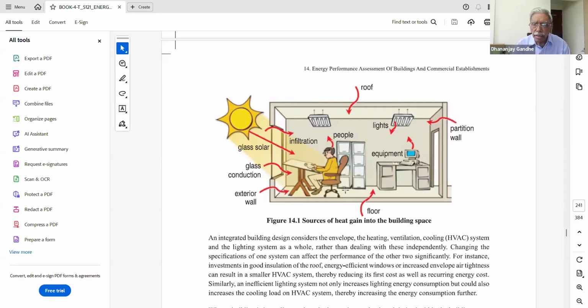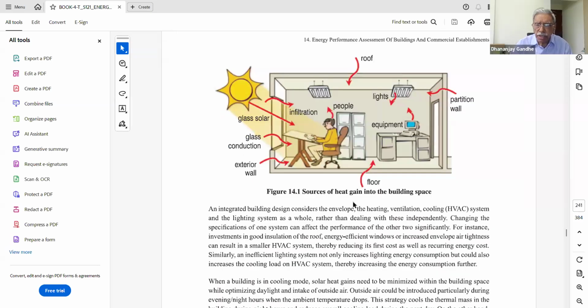In addition to that, you have the lighting system. We can see the lights over there. The light not only gives light, but also produces some heat, and that is a heat load on the air conditioning system. Also the equipment that is used, the computers, also generates heat. All of us know that a laptop has a fan because there is some internal heat developed. So heat is generated even by laptops and computers and other devices in the office, maybe the printer. And the people sitting and working in the atmosphere also constitute a load on the system. So this explains the sources of heat gain into the building envelope, in the room envelope. Okay, so all these loads we have to assess, we have to calculate the heat loads and take this value for further assessment.